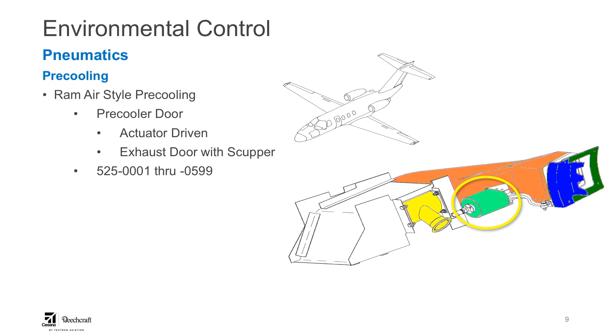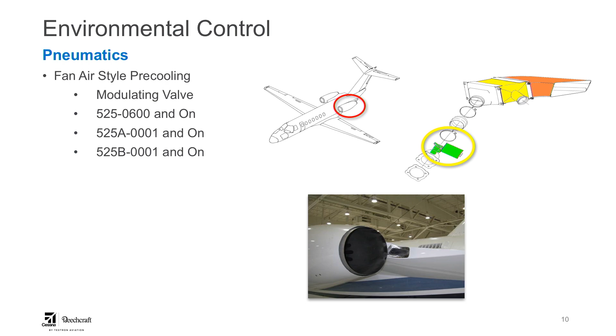Now, as I mentioned, that was kind of the exception. Here's the rule. On 525 serial 600 and on, including M2, and on all 525A and 525B serials, we use the fan bypass air. There is a modulating valve shown here that actuates using service air pressure, and it controls how much flow comes into the inlet of the pre-cooler. So instead of controlling the escape, we control the inlet, and that is coming straight off the engine.